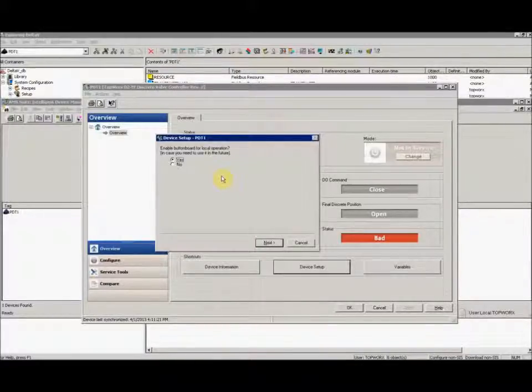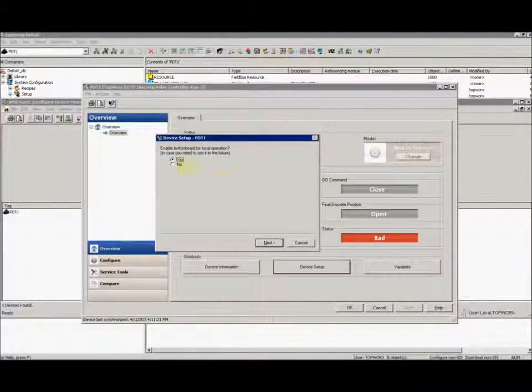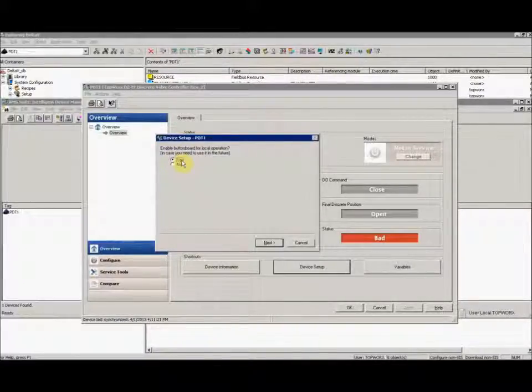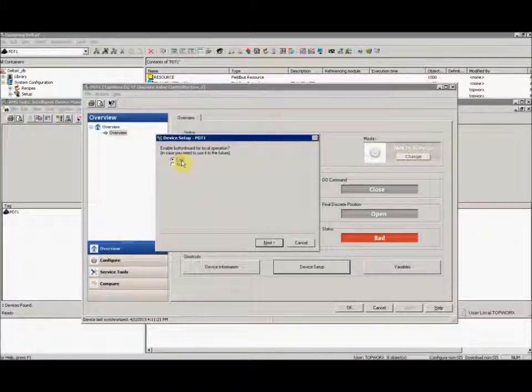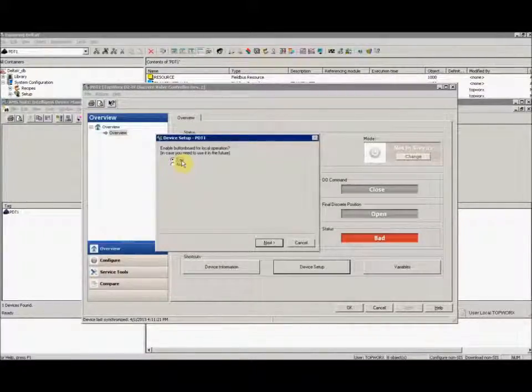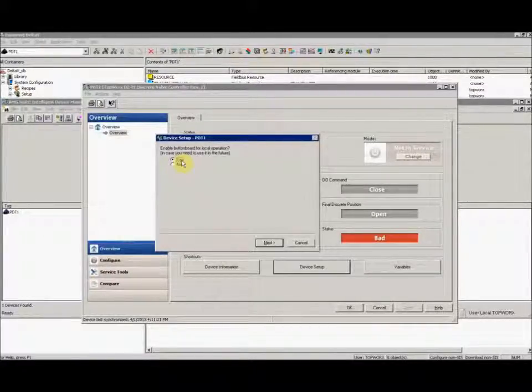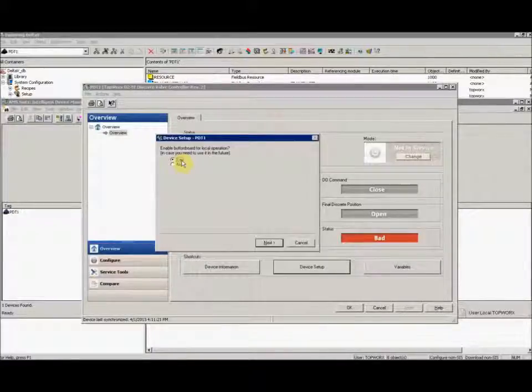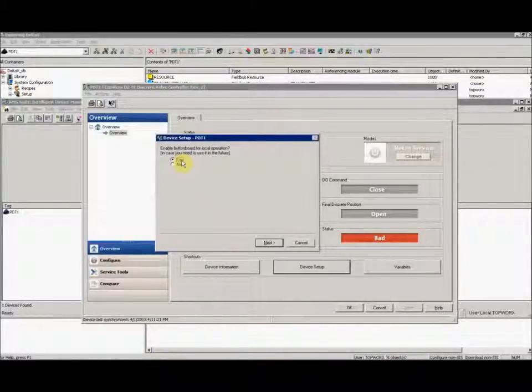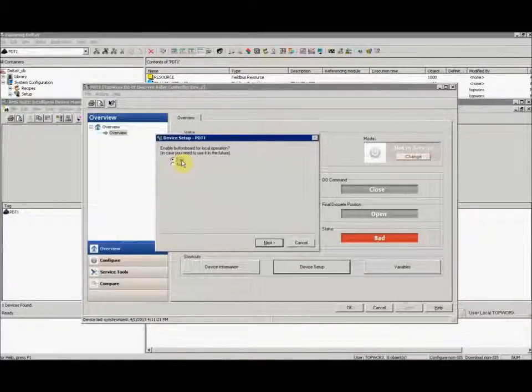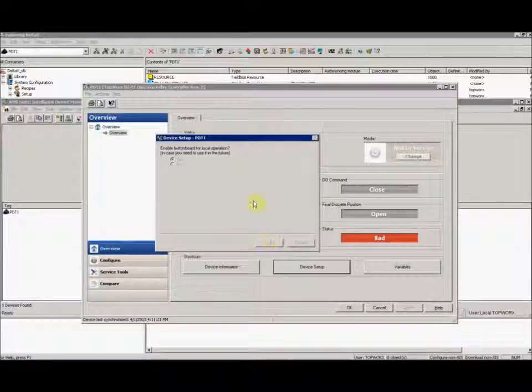Now it's asking us if we want to enable the button board for local operation. I'll select yes. Once again, just a reminder, this will only enable the button board for use when the resource and transducer block are out of service. This way no one can pop the lid in the field and change settings in the device. We'll hit next.